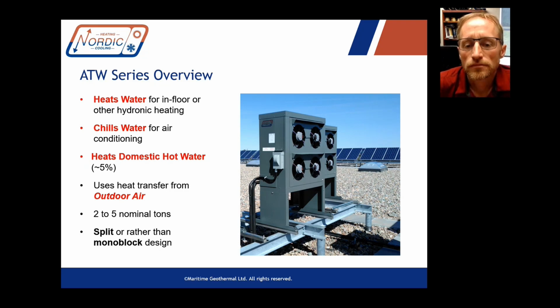Sorry for interrupting. Andrew and I did a comparison of a bunch of the different air source heat pumps that are on the market. Are you able to provide us with a curve for your heat production and COP against outdoor temperature? There's actually a curve. We don't usually present it as a curve because there are detailed performance tables in the manual, and I'll show you where to find that as well. But there's actually a curve in this presentation just to see how the capacity and COP vary with outdoor temperature. Oh, excellent! Thank you. So we'll get there in a few minutes.